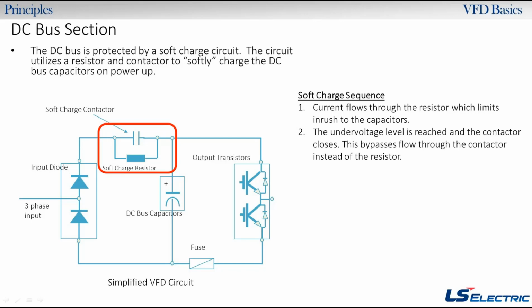So the purpose of this soft charge circuit is you have a resistor, which you can think of as like a valve. It's going to restrict how much inrush goes to that capacitor, or really there'd be more than one capacitor there. And then you also have a soft charge contactor. So current is going to flow through this resistor, and that's going to limit the inrush current. Then as that voltage slowly charges up, or softly charges up, it's going to reach an undervoltage level point, and then this contactor is going to close. And if you know just basic stuff about electronics, the path of least resistance is the way that everything flows. So there's no resistance here, and there is a resistor there. So everything's going to flow through the contactor. It's kind of like a little bypass, and then it'll charge up the capacitors the rest of the way.